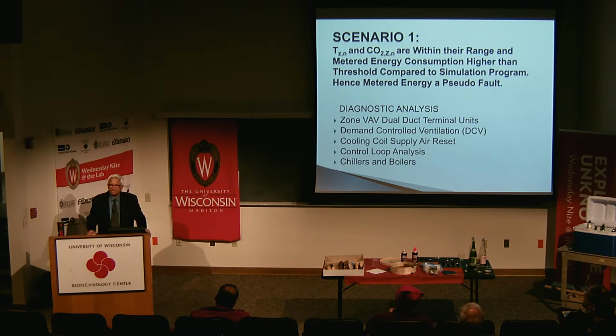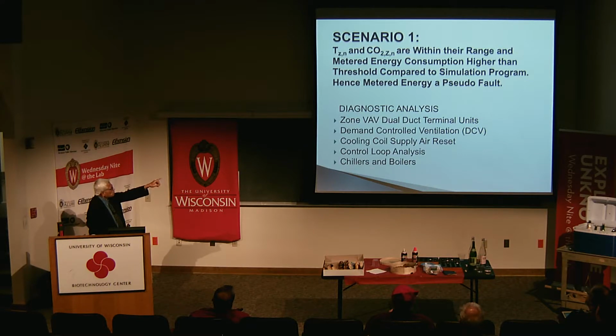It's something like the energy consumption for your residential homes. You may find this month's monthly bill is higher than what you had for the same month last year. It could be you are opening doors more, or you have parties, you are having a lot of lights going on. So in that case, the metered energy consumption for you is accurate, but it's a pseudo fault, and you have to diagnose what the causes are. Something similar I am doing here. So these are the possible approaches I took as to what can be done, what things are responsible for increased energy consumption that results in the higher metered energy consumption.